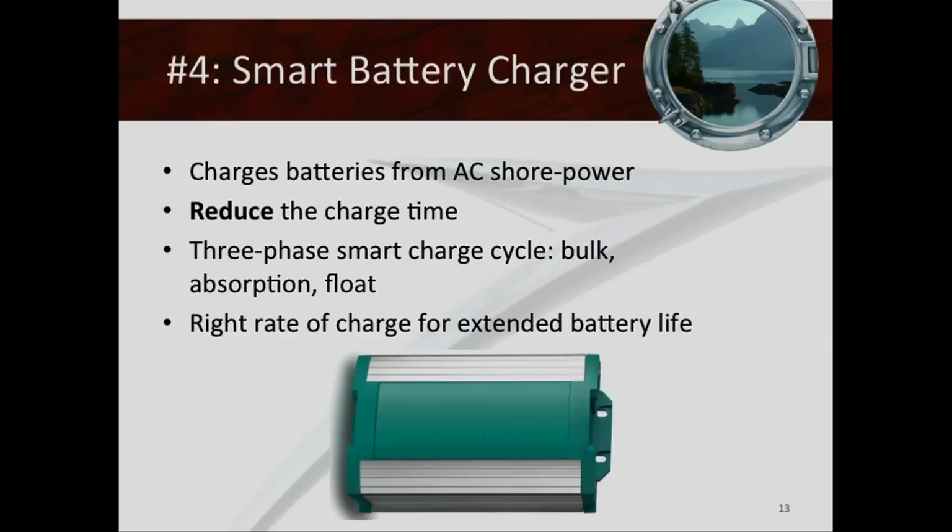Trickle charge is not a word that's used anymore. It's just a word. It doesn't mean anything. But they got it wrong by about 0.1, 0.2 volts, and it would actually boil your batteries slowly. It's kind of like death by a thousand paper cuts, or eating a grain of rice, or water torture. Just one drop on the forehead will drive you nuts. You're thinking, well, what's the big deal? Well, it's not a big deal for 24 hours or 48 or a week. But if you leave it on for 4 months, that battery will boil over. And it happens all the time. People are like, oh, damn it, I left it on. And then they've got to change 6 golf carts, 8 golf carts.